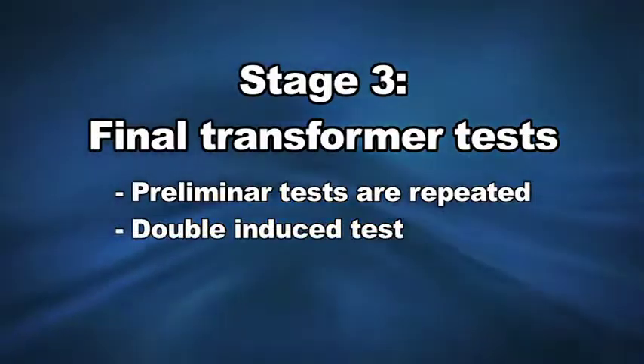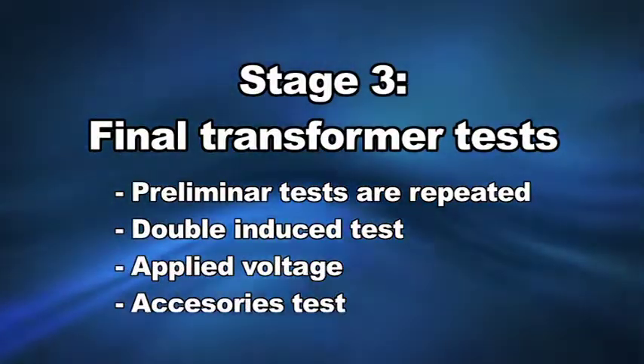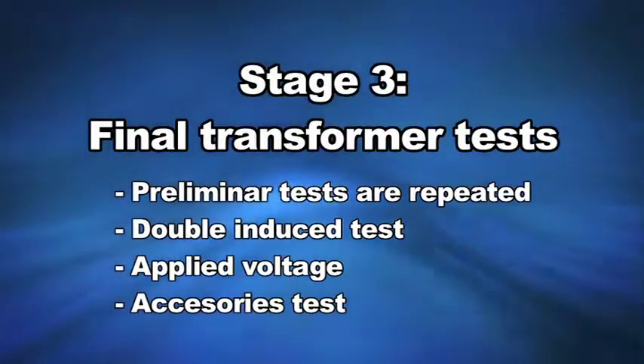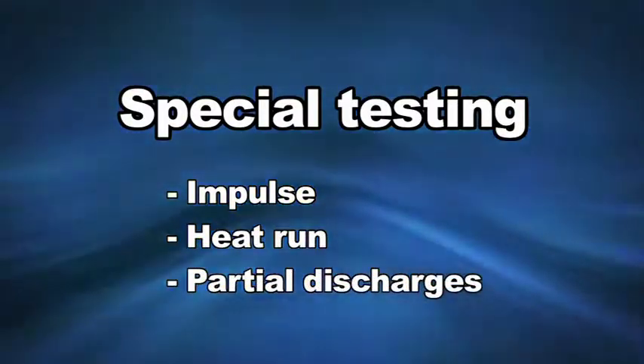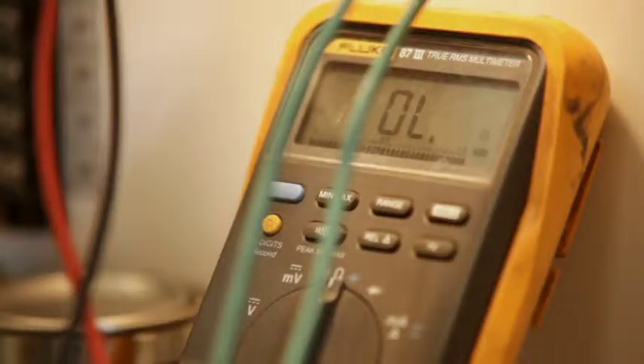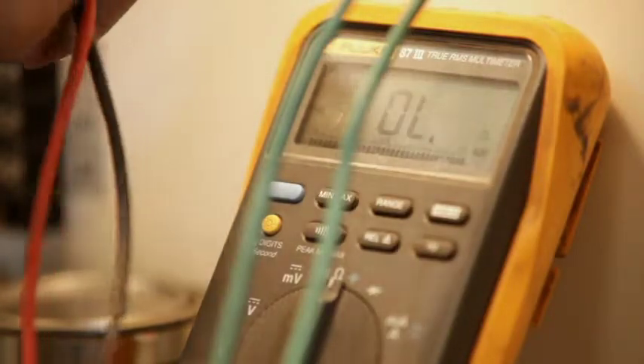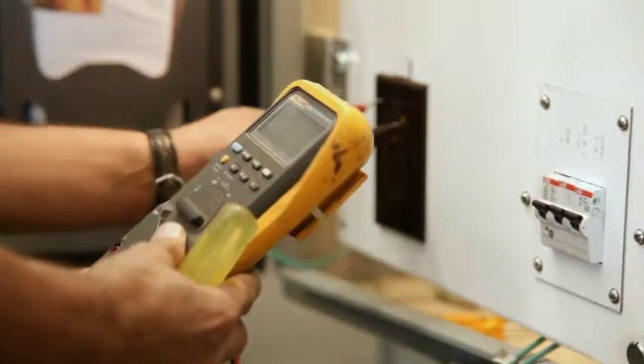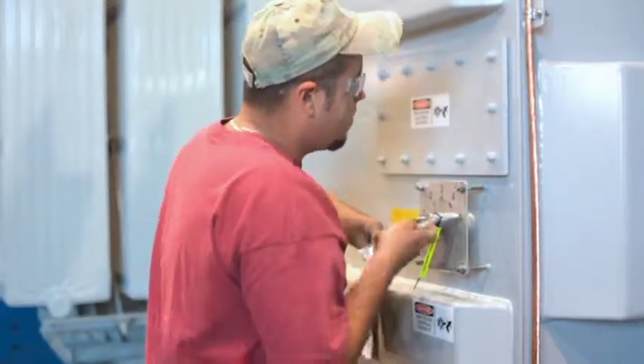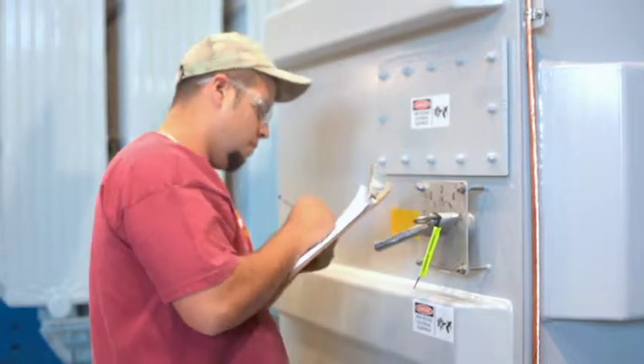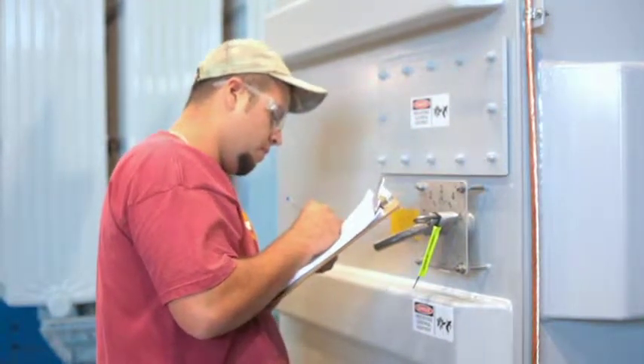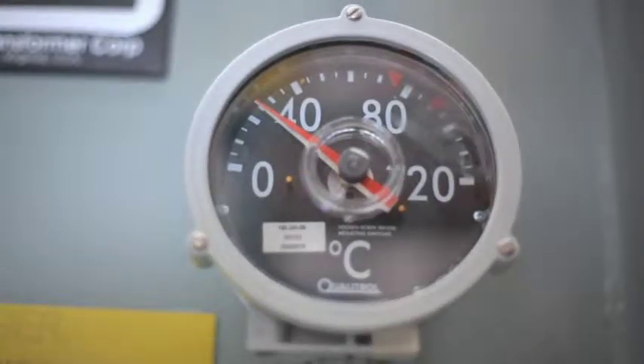Preliminary tests are repeated, and the double induced test is also performed, as well as the applied voltage and accessories testing. We are capable of performing special testing in order to meet the strict industry requirement standards, such as impulse, heat run, and partial discharge tests. During the final inspection of the transformer, it is verified that the transformer complies with all the measurements on the 101 sheet drawing, also called the customer sheet. It verifies the installation of all the required accessories stated in that sheet, as well as proper operation. Also, the calibration of temperature gauges is carried out.